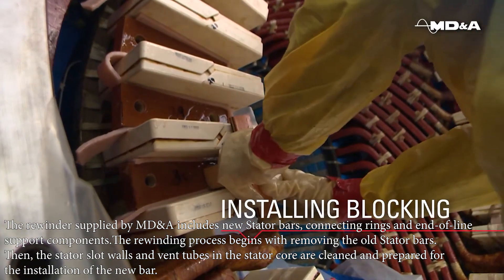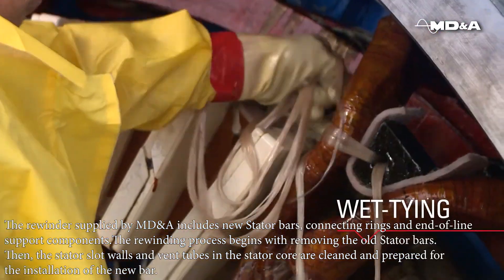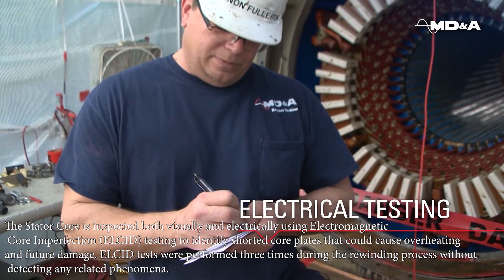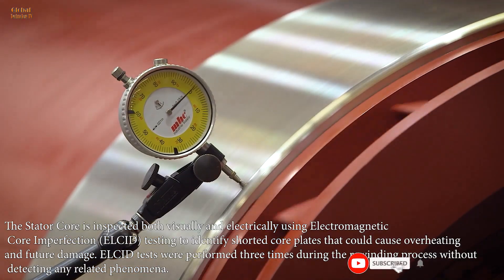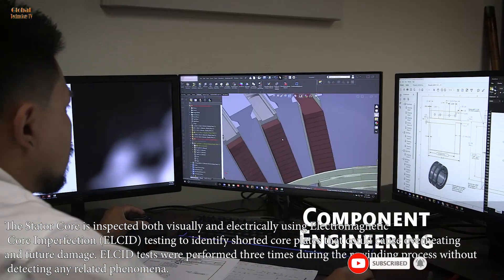Then the stator slot walls and vent tubes in the stator core are cleaned and prepared for the installation of the new bar. The stator core is inspected both visually and electrically using electromagnetic core imperfection (ELCID) testing to identify shorted core plates that could cause overheating and future damage. ELCID tests were performed three times during the rewinding process without detecting any related phenomena.